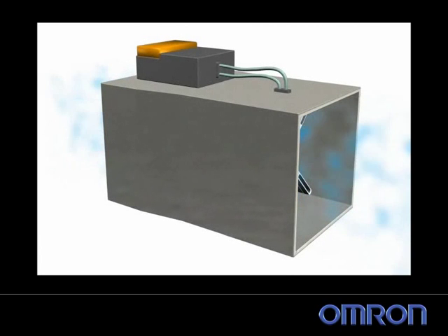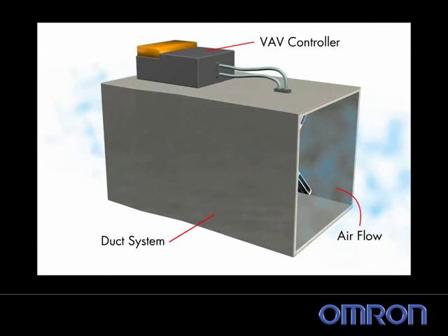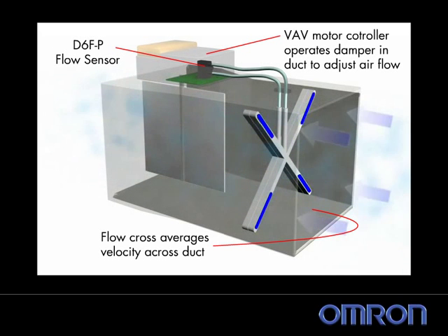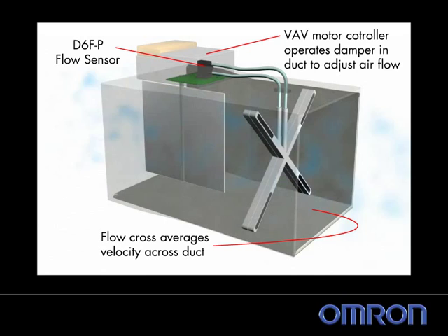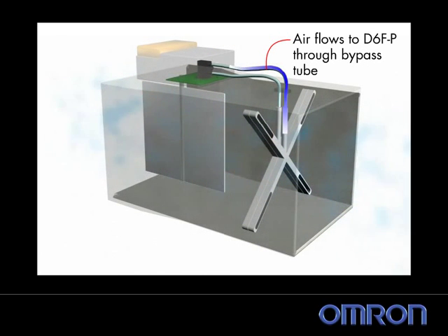In this bypass example, a variable air volume controller used to adjust air flow in multi-zone commercial buildings uses a D6F-P flow sensor for feedback and control. The mass flow sensor's high resolution at low flows is particularly beneficial in the HVAC industry, as lower velocities are used to reduce noise and to ensure sufficient fresh air is being introduced.